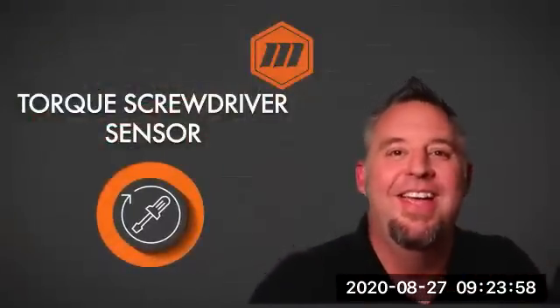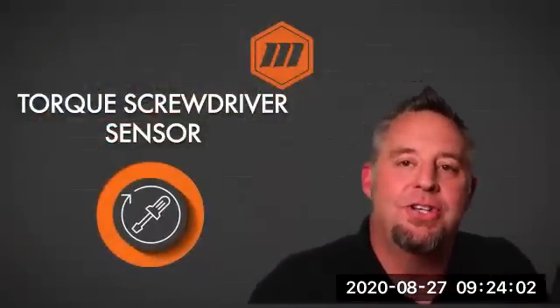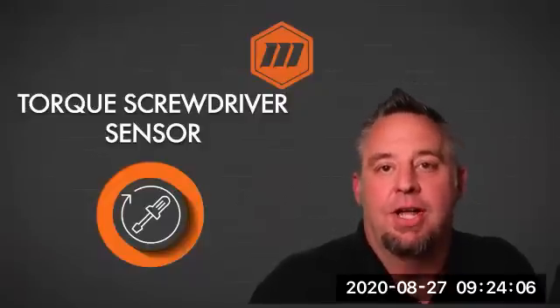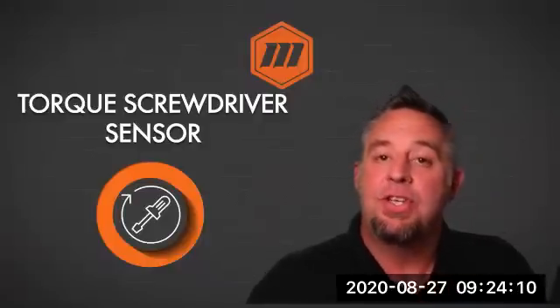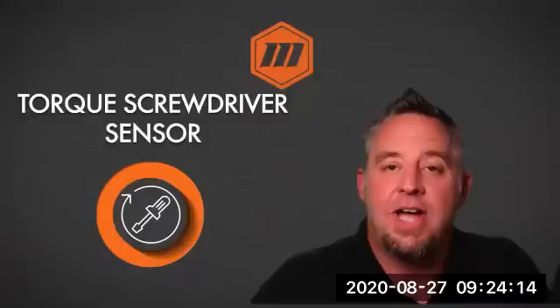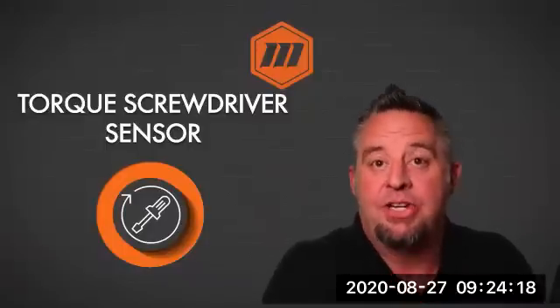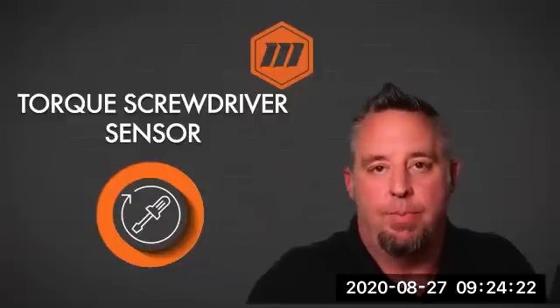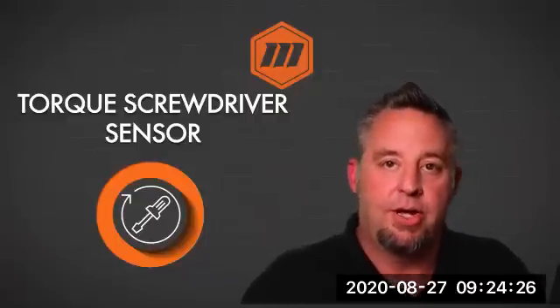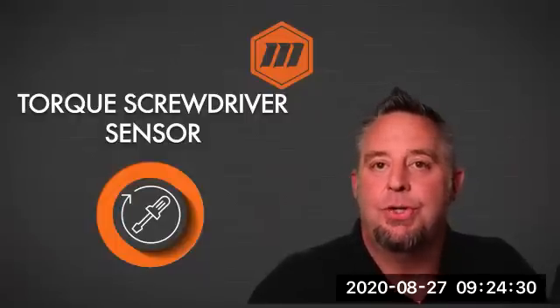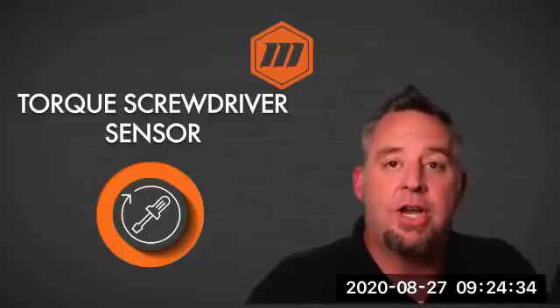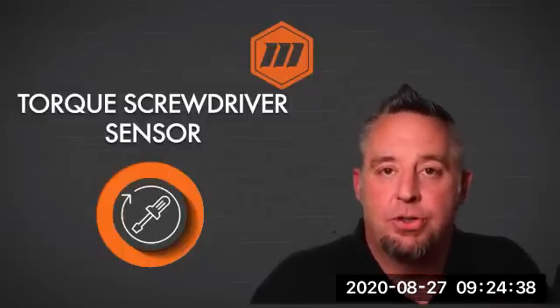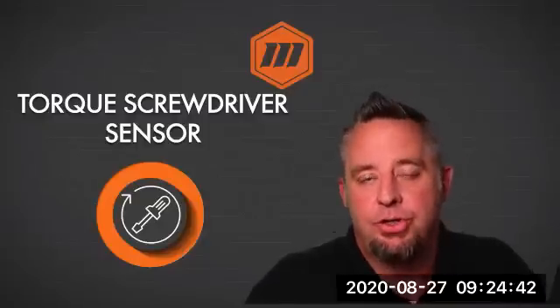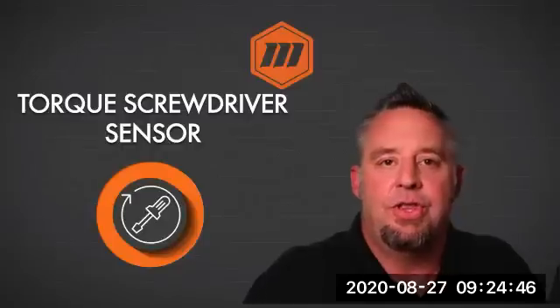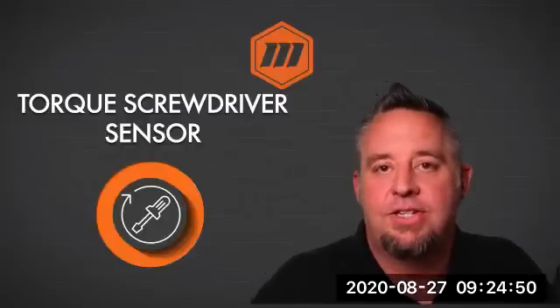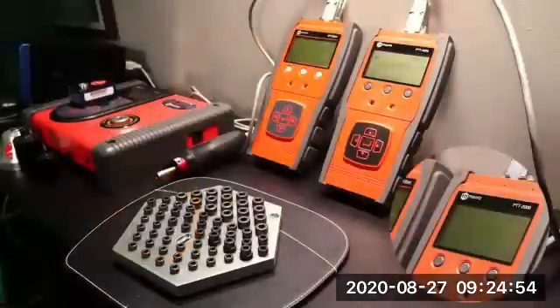All right, so our last torque transducer is the torque screwdriver analyzer sensor. With this screwdriver, you can use it as an R&D device. You can look at managing your application to see where a part may fail. If you are seeing issues with a specific application, you can also use this for joint auditing or fastener auditing after a particular fastener has been torqued. You could do a breakaway test, and you could also do a first movement test with this. The torque screwdriver has the sensor built into it, so let's take a look at what that sensor looks like.